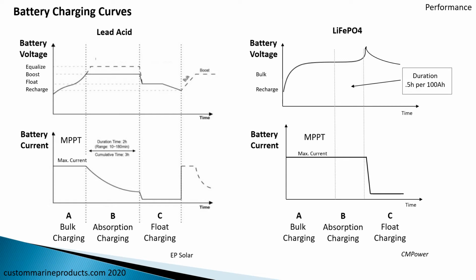If we compare the charge and discharge of batteries of lead acid versus LiFePO, they look quite different, the charge curves. So if we look at lead acid, we have 3 phases of charge. We have what's called a bulk charge, where the battery is taking a maximum amount of current that it can accept to get up to a voltage of maybe 12.8 volts. That voltage is held constant, but as the lead acid charges, its charging efficiency decreases and it can accept less current.